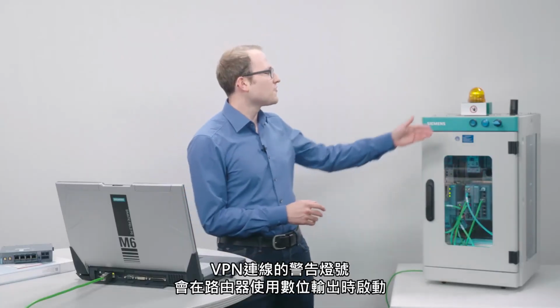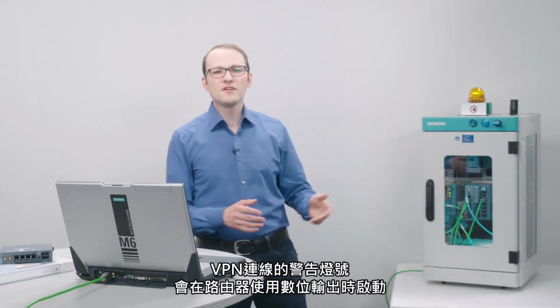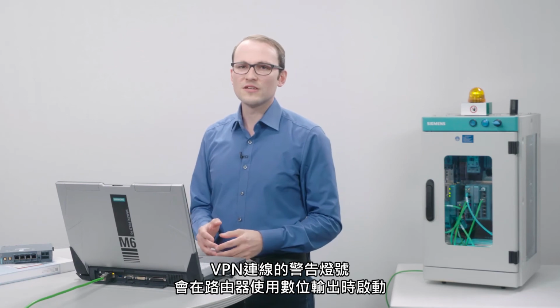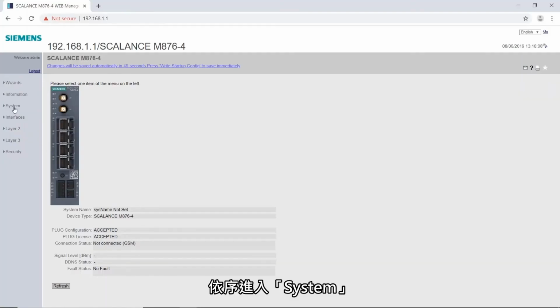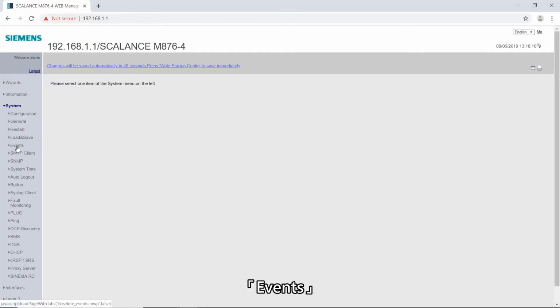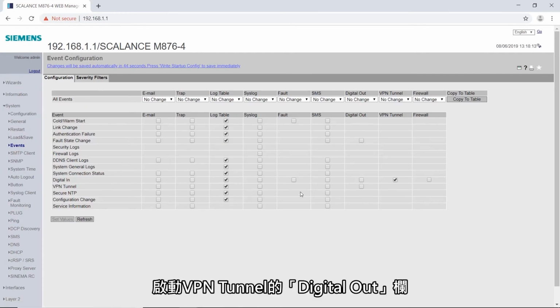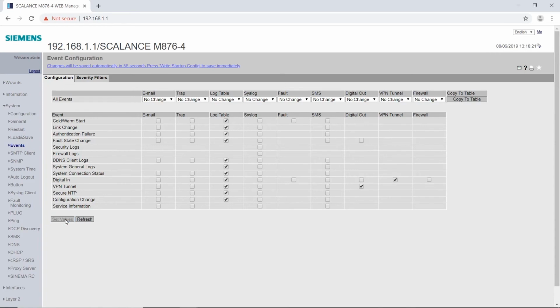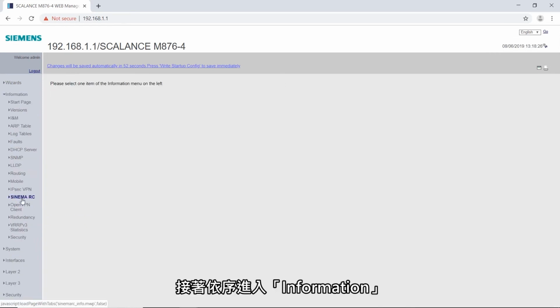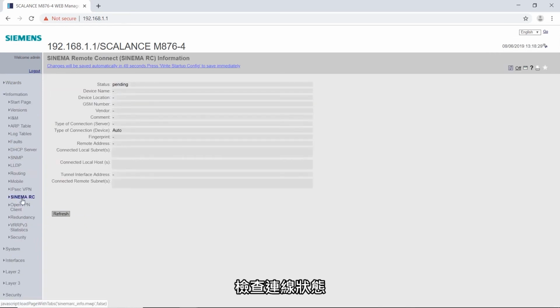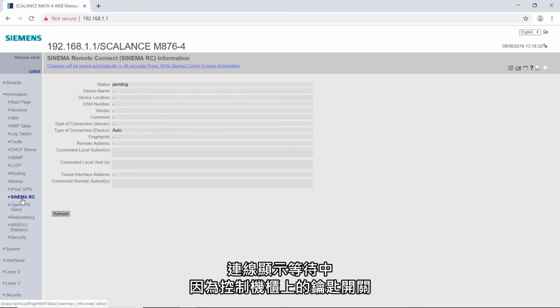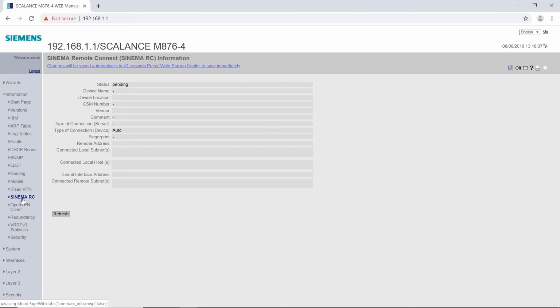The warning light for the VPN connection is to be activated from the digital output of the router. Therefore, under System, Events, I activate VPN tunnel in the column Digital Out. Under Information, SINEMA RC, I can check the status of the connection. The connection is pending because the key switch on the control cabinet has not yet been activated.